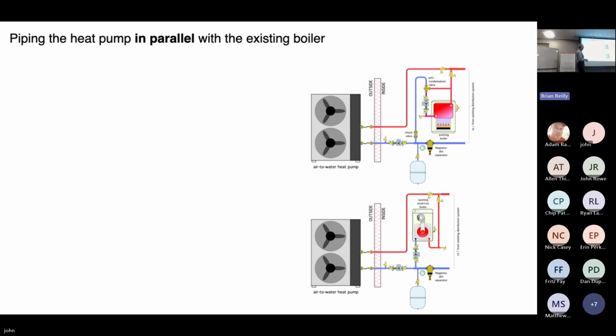So this shows, let me actually start with this one down here. This is a modulating condensing, or what we call a mod-con, boiler. Typical wall-hung gas-fired, it could operate on propane as well. It's got its own circulator with a check valve. The boiler actually turns on the circulator. So here's the cool water coming back from the system. If the boiler was the sole heat source, the flow would be up through the boiler and back to the system. If the heat pump were the sole heat source, the cool water would come back, and the heat pump is running its own circulator here. That pumps the water through the heat pump and out to the system. So either heat source could operate as the sole heat source, or they can operate together.